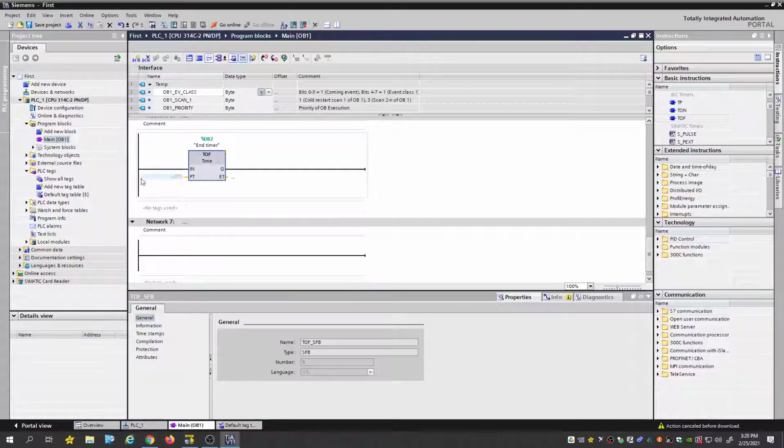So what we could do is have a light that's enabled here, and then for instance we want the motor to run for 5 seconds once we disable the timer. That's how a timer off delay works: you have to enable it. Once it's enabled, you kill the rung by disconnecting whatever input is feeding the timer. Once you do that, the timer starts to time for the amount of time you have set here, in this case 5 seconds. And once it's actually done, it goes off.